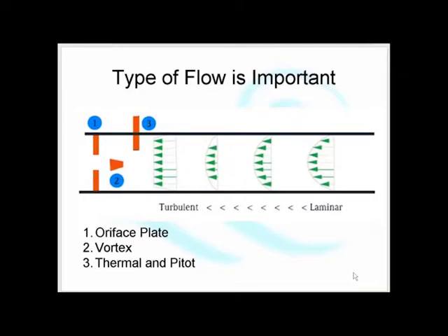If you think that the vast majority of our flow meters are in actual fact measuring velocity, then what comes out of this is, if we're measuring velocity in one specific point, and we were to measure velocity on a flow profile which is laminar flow, it would make a difference whether we were measuring in the middle there or whether we were measuring at the edge.